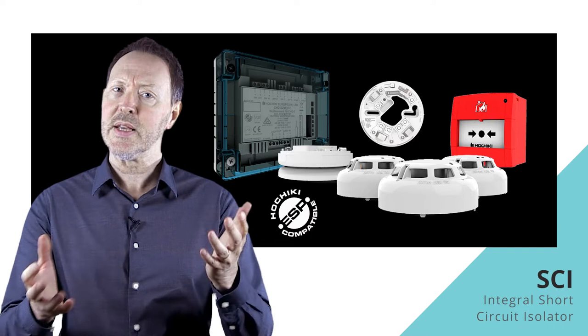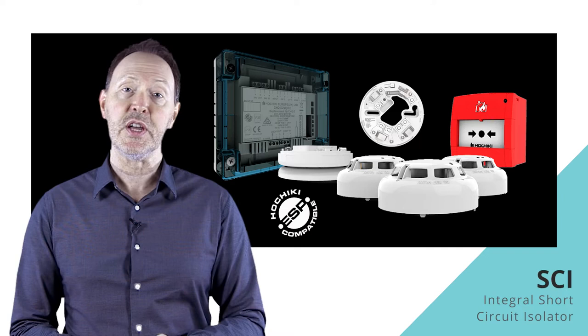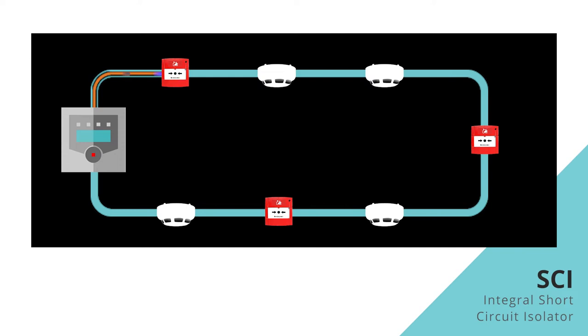On a healthy addressable fire system, the voltage from the fire control panel is driven one way around the loop, powering devices and carrying data. Loop cables can be accidentally damaged by tools or other equipment, particularly if not mechanically protected by conduit. If the positive and negative conductors within the cable come into contact with each other, that voltage level drops. This is a short circuit.